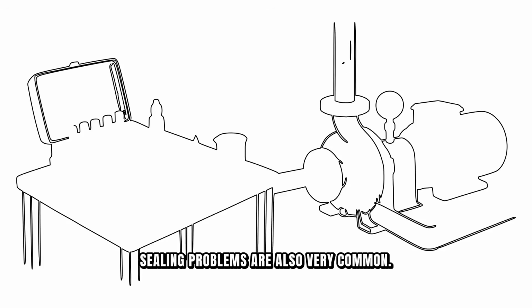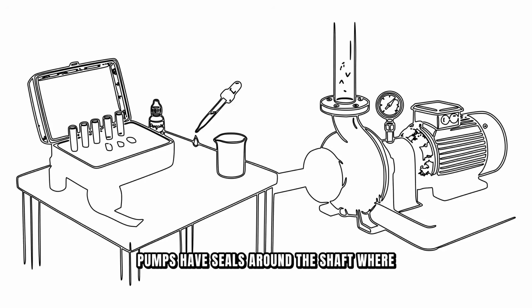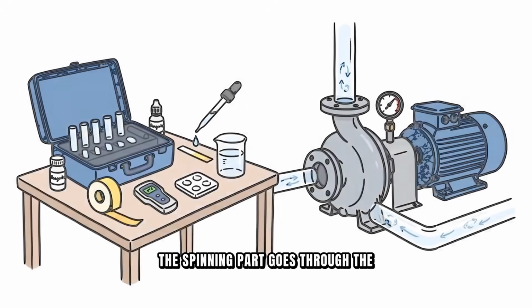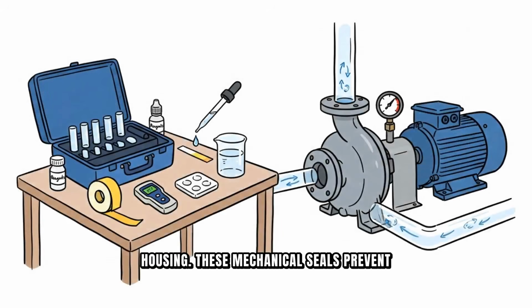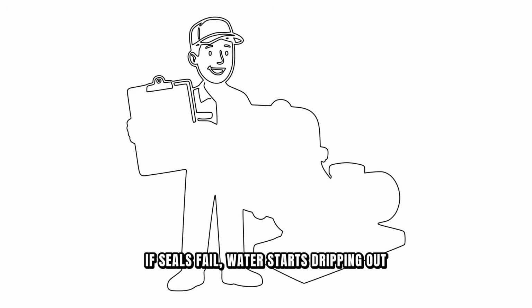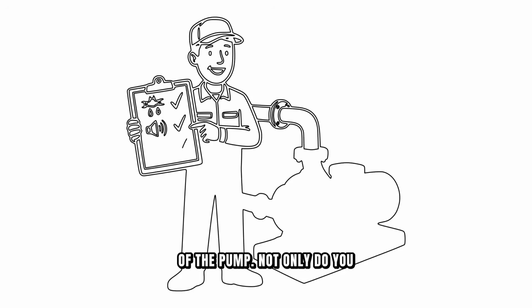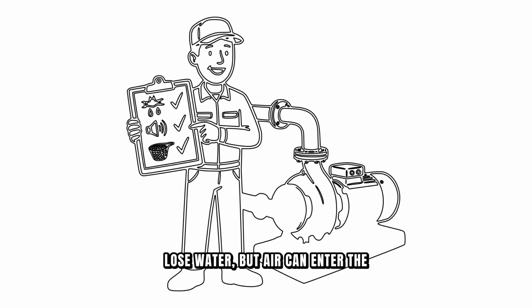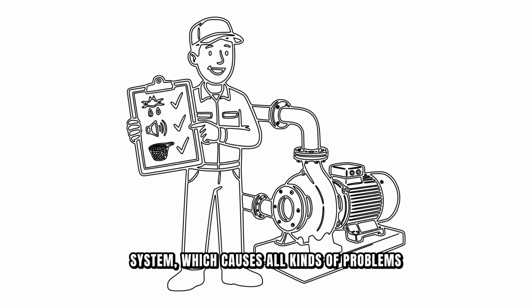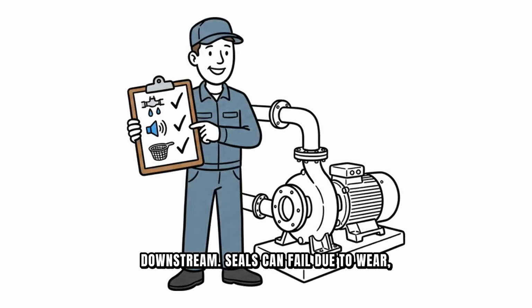Sealing problems are also very common. Pumps have seals around the shaft where the spinning part goes through the housing. These mechanical seals prevent water from leaking along the shaft. If seals fail, water starts dripping out of the pump. Not only do you lose water, but air can enter the system, which causes all kinds of problems downstream. Seals can fail due to wear, misalignment, cavitation, or contamination from particles in the water.